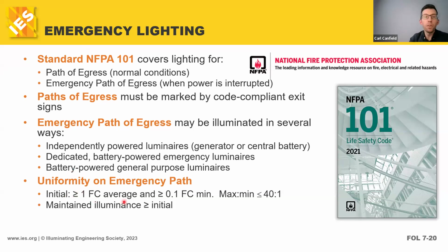So people need to be able to see if there is a fire, if there's a power outage, that is where the emergency lighting system comes into play. And NFPA 101 tells us that system has to provide an average of 1 foot candle along that path of egress, right? And a minimum of 0.1 foot candles.